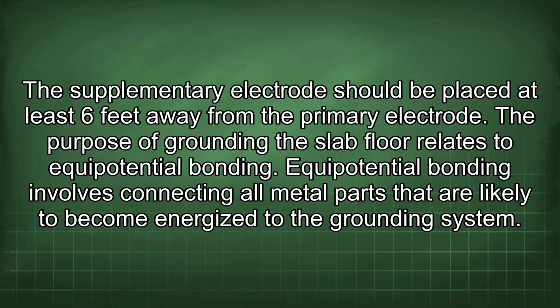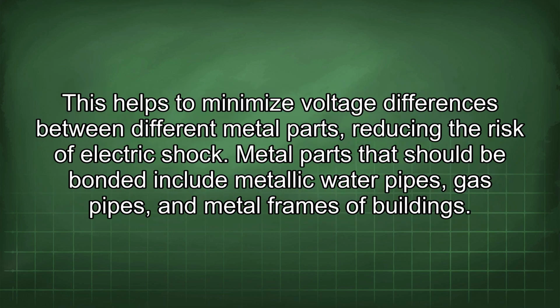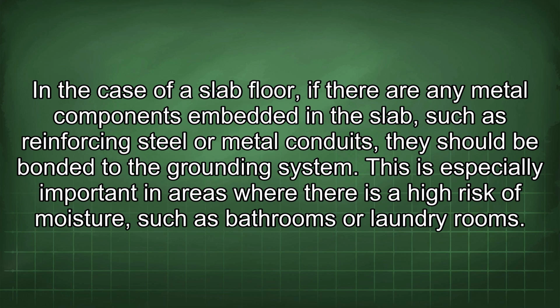The purpose of grounding the slab floor relates to equipotential bonding. Equipotential bonding involves connecting all metal parts that are likely to become energized to the grounding system. This helps to minimize voltage differences between different metal parts, reducing the risk of electric shock. Metal parts that should be bonded include metallic water pipes, gas pipes, and metal frames of buildings. In the case of a slab floor, if there are any metal components embedded in the slab, such as reinforcing steel or metal conduits, they should be bonded to the grounding system. This is especially important in areas where there is a high risk of moisture, such as bathrooms or laundry rooms.